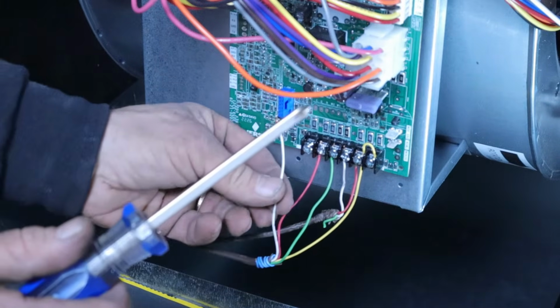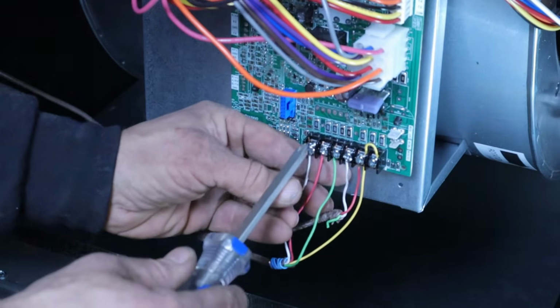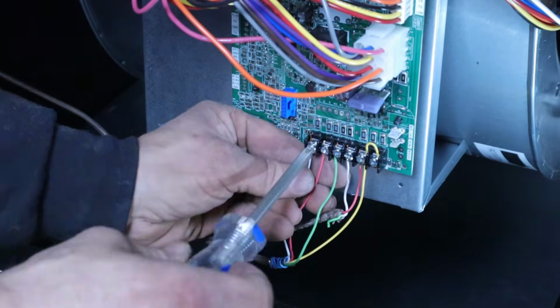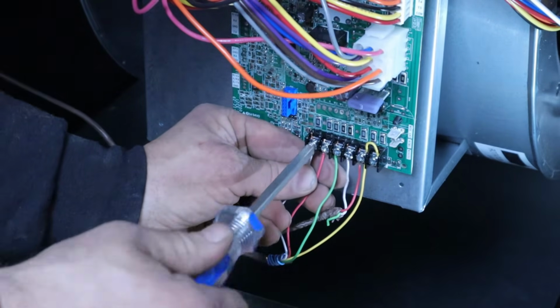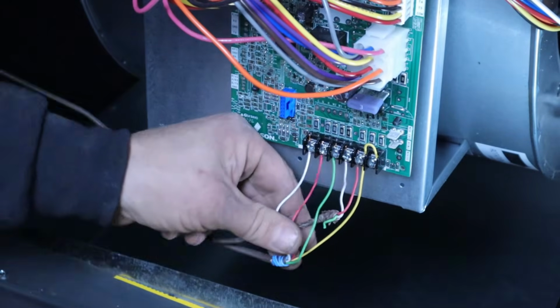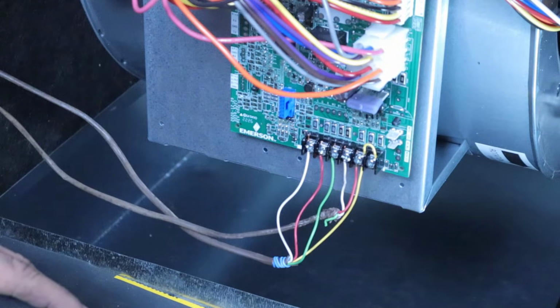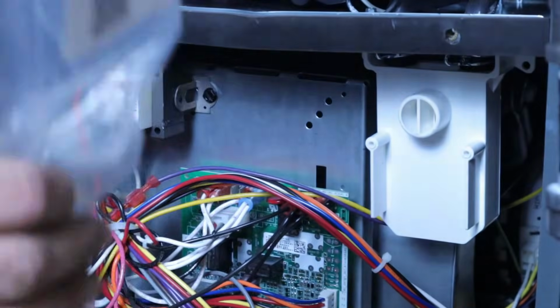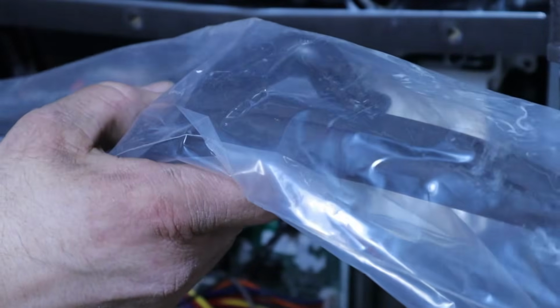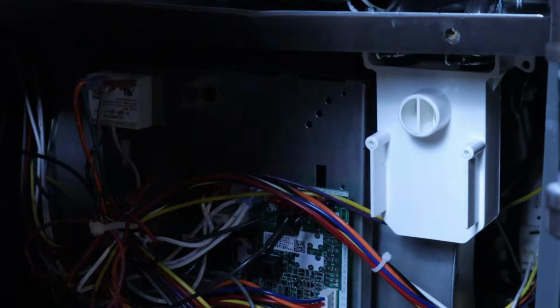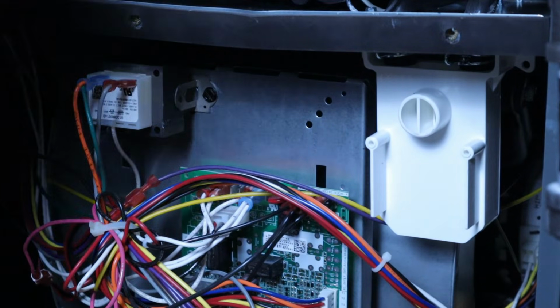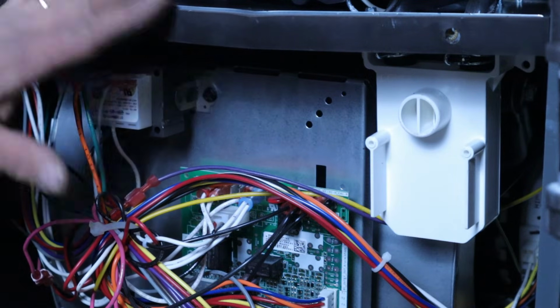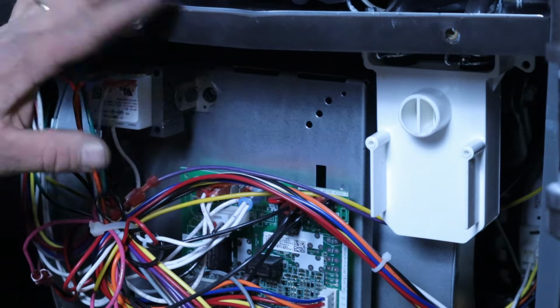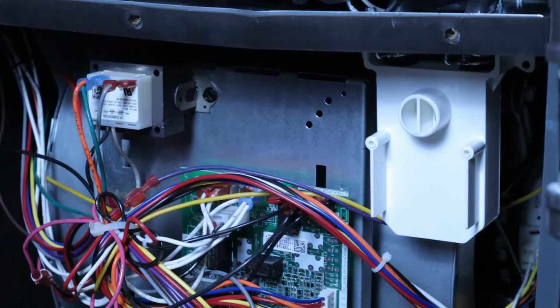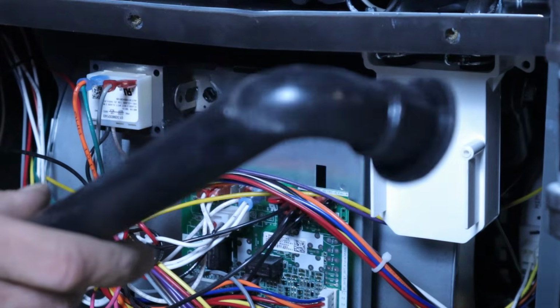So now what we have is our white, and I'm going to hook that up to W, and that's for our heating. And that's going to start up our 90% furnace. And that's it. Our low voltage wiring is done. Now when you open up these 90% furnaces, you're going to find a whole bag full of rubber hoses and fittings in it. Most of those hoses are for a configuration where you might have this furnace laying on its side rather than straight up like this. So the only thing we really need is this kind of long hose right here.